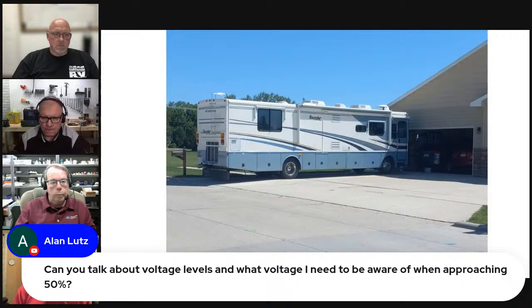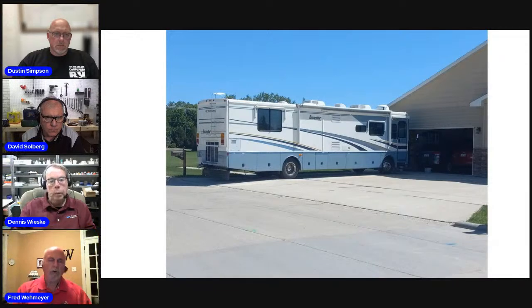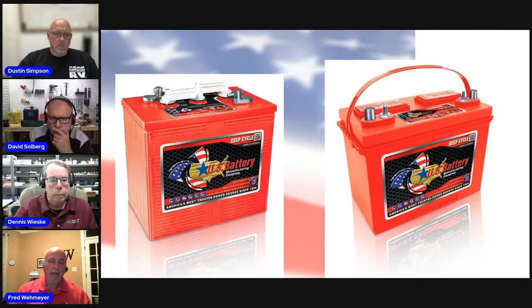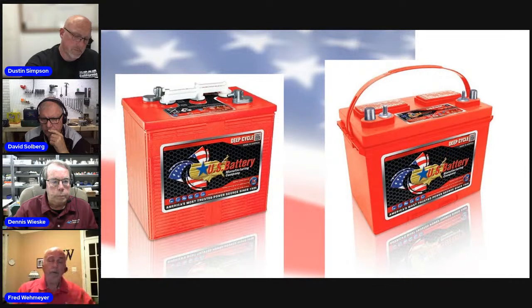So that would be on the DC side, obviously. Typically on a 12-volt system, if you have a low voltage cutoff, that will terminate discharge automatically. Typically, depending on the magnitude of the load, at about 50% you'll be right around 11.5 volts on a 12-volt system. A full discharge would be 10.5 volts.